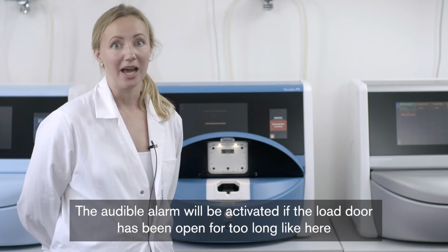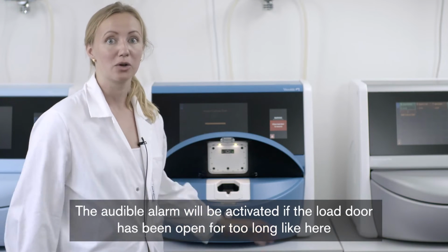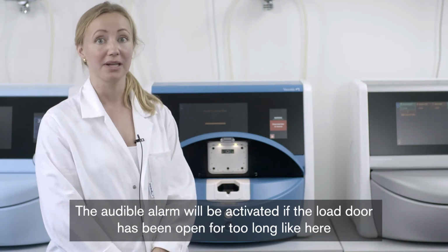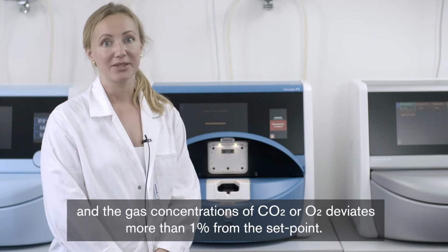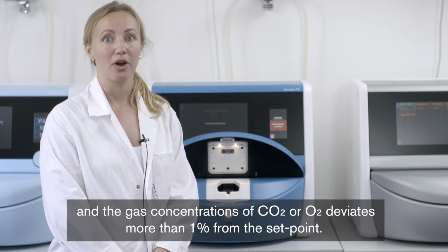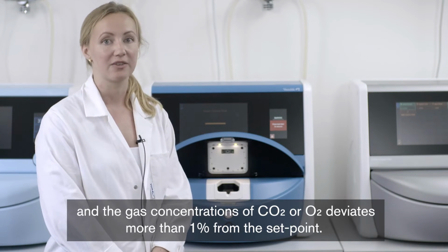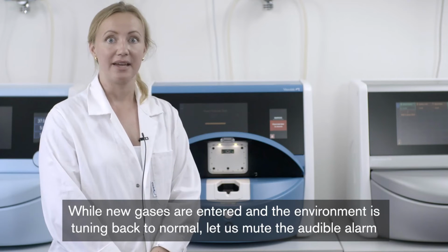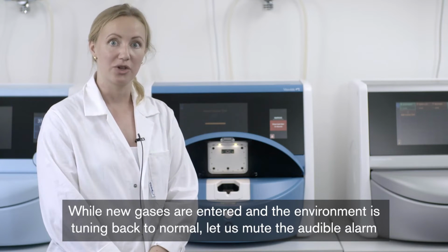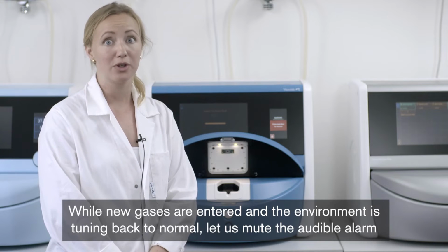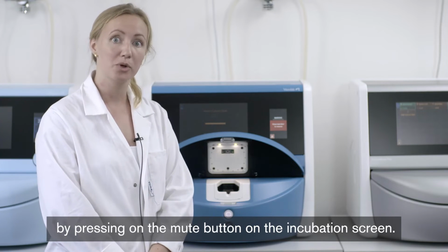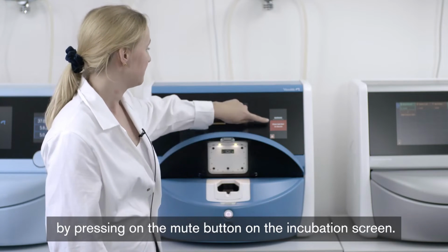The audible alarm will be activated if the load door has been opened for too long, like here, and the gas concentration, CO2 or oxygen, deviates more than 1% from the set point. While new gases are entered and the environment is turning back to normal, let us mute the audible alarm by pressing on the mute button on the incubation screen.